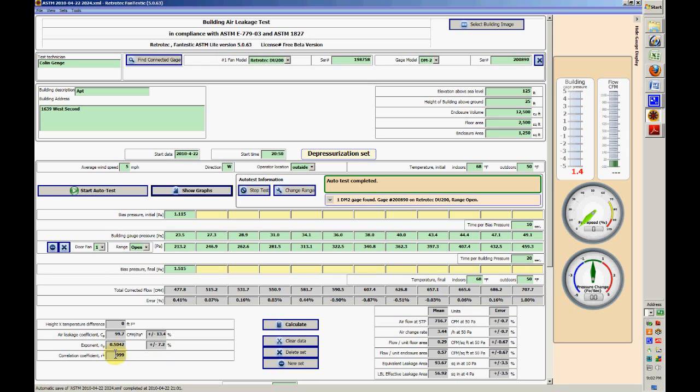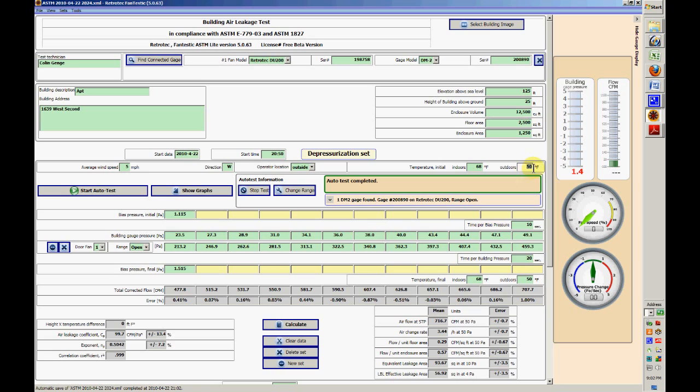It has an exponent of 0.5, which is—it's a square hole in the box, that's about right. 0.999 correlation, which is excellent, and the errors on each point are relatively small. I'll just put the right pressure in here. It's actually the same temperature inside and out, so we'll just call this 68, recalculate.